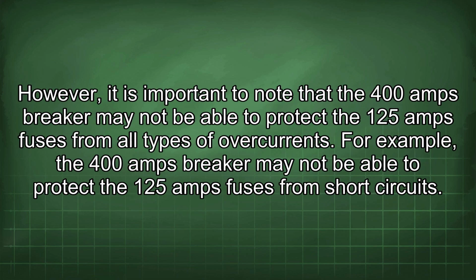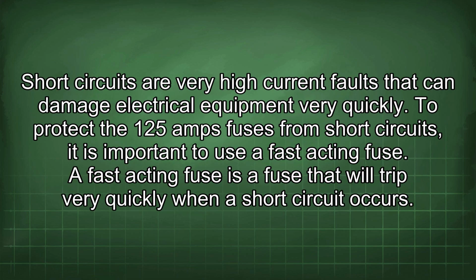However, it is important to note that the 400 amps breaker may not be able to protect the 125 amps fuses from all types of overcurrents. For example, the 400 amps breaker may not be able to protect the 125 amps fuses from short circuits. Short circuits are very high current faults that can damage electrical equipment very quickly. To protect the 125 amps fuses from short circuits, it is important to use a fast-acting fuse. A fast-acting fuse is a fuse that will trip very quickly when a short circuit occurs.